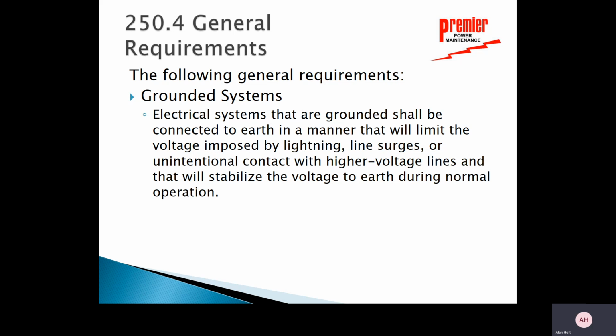Okay, Section 250.4, general requirements. There are some general requirements on grounded systems. Electrical systems that are grounded have to be connected to earth, solidly connected to earth in such a manner that will limit the imposed voltage by lightning or line surges or unintentional contact with a higher voltage, and that will stabilize the voltage to earth during normal operation. So I want to have a solid location for a ground path for current to flow, and it has to be solidly grounded there as per 250.4.